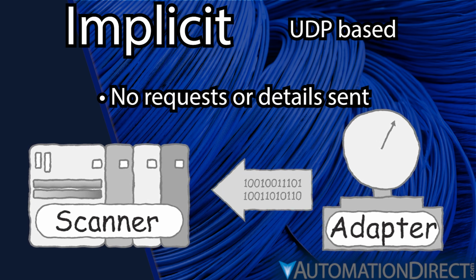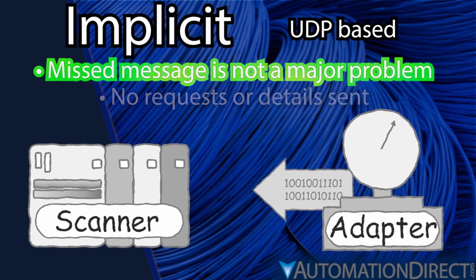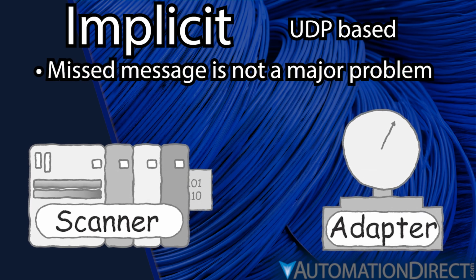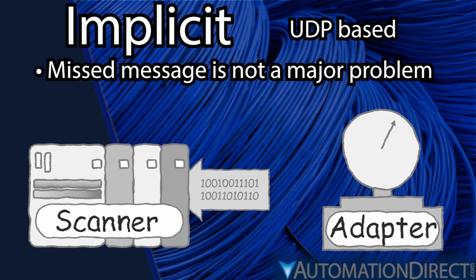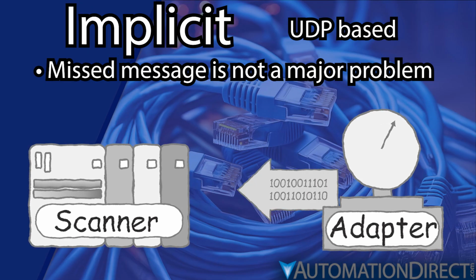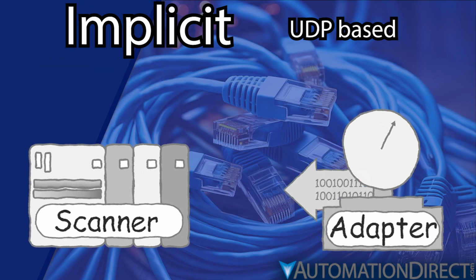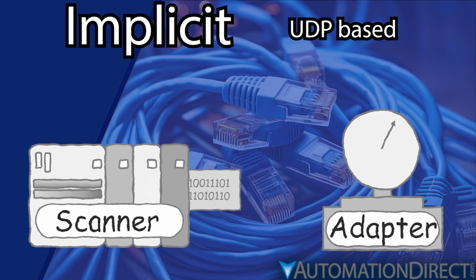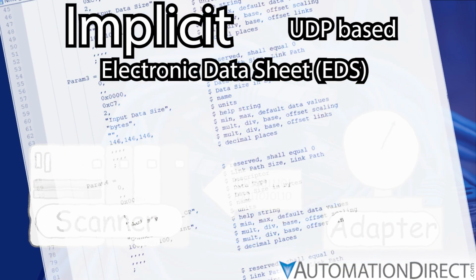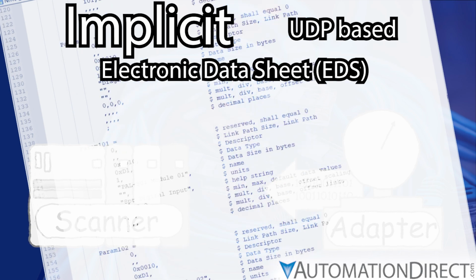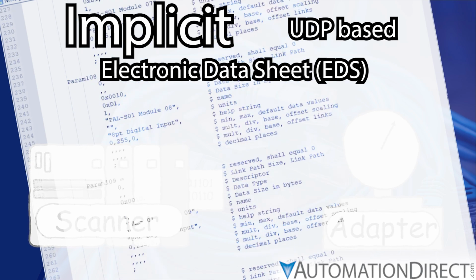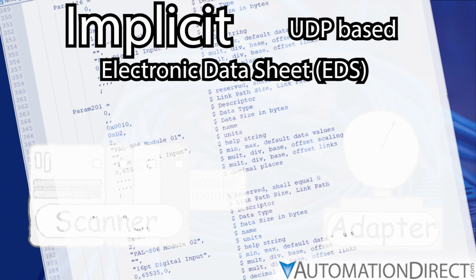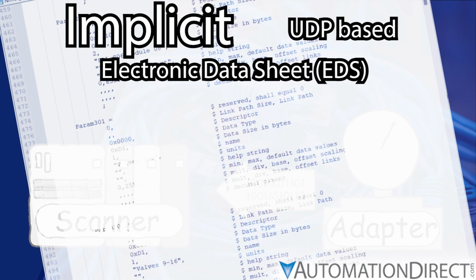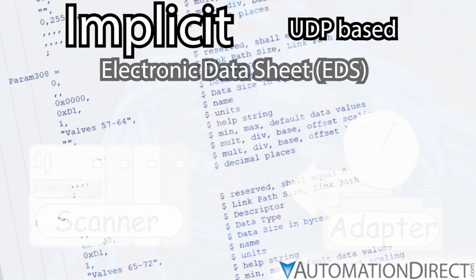Since the adapter will be sending a steady, repeating stream of data, a missed message is not a significant concern since another is on the way within milliseconds. The data the adapter sends has all been pre-configured in the scanner, either manually or by the provision of the adapter's electronic datasheet. The EDS is a simple ASCII file that identifies all the adapter's data, so the data stream's identity is understood by both devices before communication even starts.